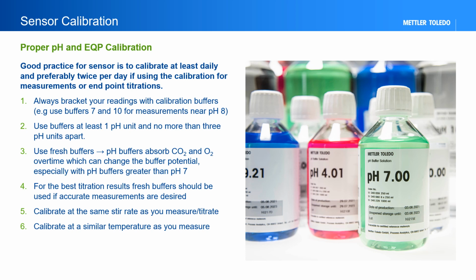One should always bracket your measured points with calibration standards. For example, calibrate with pH buffers 7 and 10 when measuring samples near pH 8. Use buffers at least 1 pH unit apart and preferably no more than 3 pH units apart. Always use fresh buffers in order to avoid air contamination, especially with buffers that are greater than pH 7. Buffers should not be reused when accurate measurements are desired.